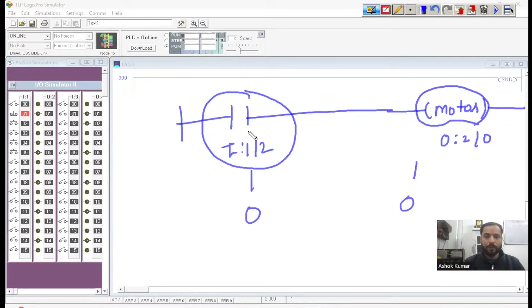In other words, you can also say if your sensor is sensing only once, giving the logic one only once, and you want the motor to stay on continuously—in that scenario, you cannot do that, because you need a continuous signal from the sensor, or from this input, to keep your motor on. I hope you're getting what I'm saying. As we know, this is a direct input category, so we need to hold it. If you replace the button with a sensor, you need a continuous signal from the sensor to keep your motor on.